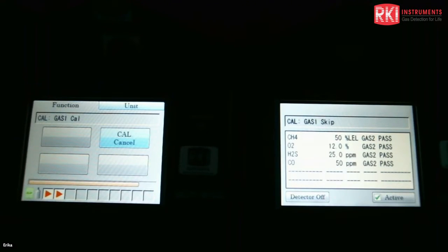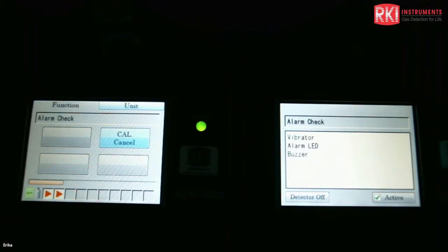I'm assuming you pressed down the red button on both of the units before you ever started. Right. If you want to do a calibration, you would want to press the gas in, gas out, the red button on top, on both instruments at the same time. Right, exactly, on pretty much all the instruments, or else you're going to get a low fail. Okay, so right now it's doing an alarm check because I've checked that option.